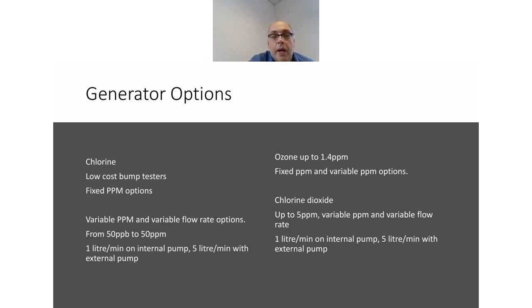There's less options for ozone, but basically we can generate ozone up to 1.4 ppm. That we do have options for fixed ppm or variable ppm output. And chlorine dioxide we can generate up to 5 ppm. Again, working on a 1 litre per minute on an internal pump. So those are sort of ranges that we're talking about with these generators. And you can see, compared to the cylinder options that I presented, that's a wide range of options, a wide range of things you can do, which you just can't do with the cylinders that we sell.